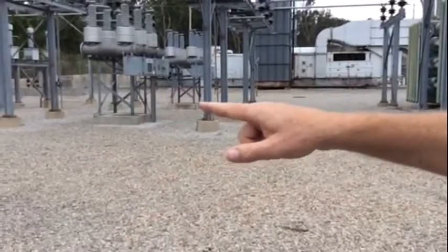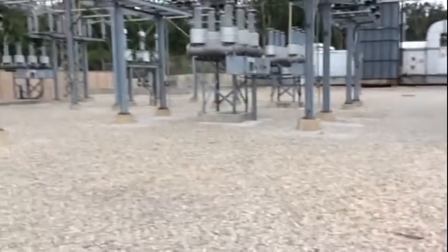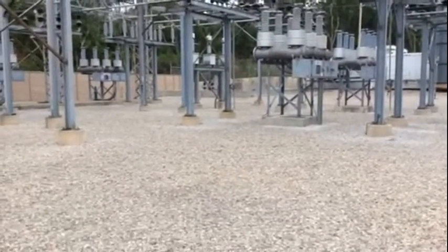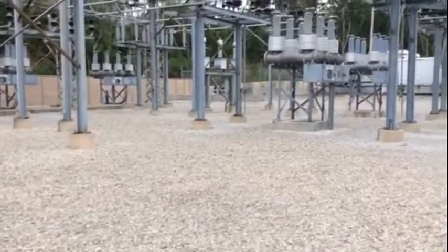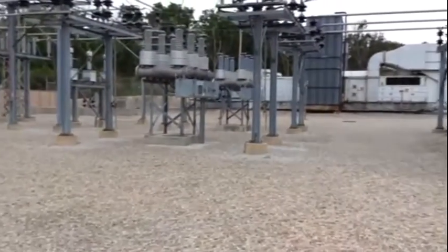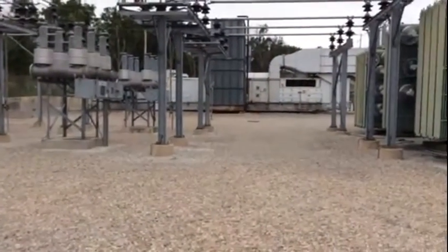Every piece of equipment, every steel structure is grounded. On concrete? It hits the mat, goes down the concrete and into the mat, and the mat is grounded. The mat is the ground. That's the copper.